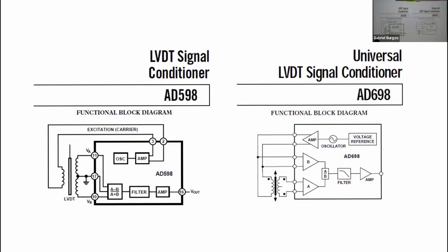Now suppose you're providing a constant voltage, which is what most LVDTs are driven with, constant AC voltage, say 3 kilohertz, just to pick a number. As that LVDT heats up, the impedance of the primary increases. Why? Because the DCR, the actual resistance of the copper winding, goes up because of the temperature coefficient of copper. The impedance goes up because the DCR goes up. The inductance doesn't change because the frequency hasn't changed, but it's the square root of x squared plus r squared. So the impedance goes up.